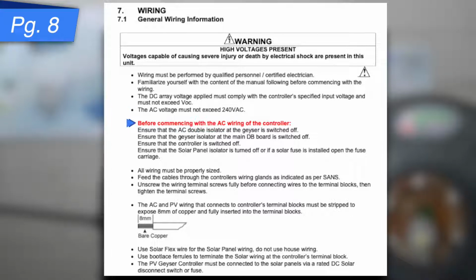Now, before commencing with the AC wiring of this controller, please ensure that everything is basically off. The AC double isolator, the geyser is off, the geyser isolator at the main DB is off, the controller is switched off, and that the solar panel isolator is all switched off. Please make sure your wiring is correctly sized and make sure that the connections go through the control wiring glands as is required by SANS.